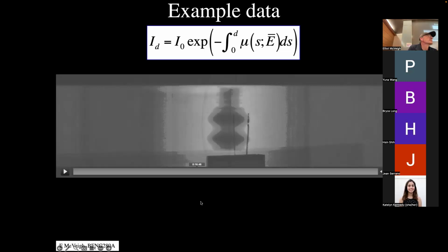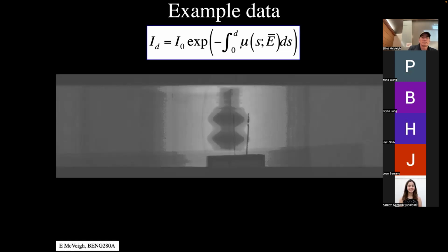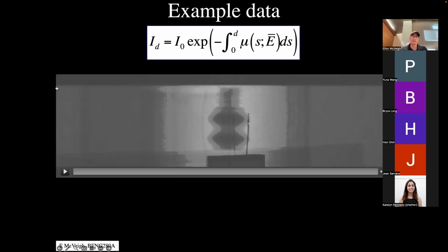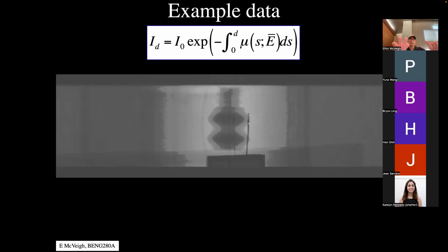In this picture, where's the source and where's the receptor? Oh, the receptor or the detector is this thing here. It's two-dimensional. It has 256 detectors in this direction. It has 832, I want to say, in this direction. So it's a two-dimensional detector grid. And that's what I'm looking at. And the source is, if I pull that back to my nose, my source is here and it projects through that way. This is like standing and looking from the source down at the object.